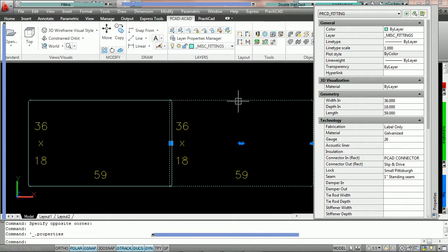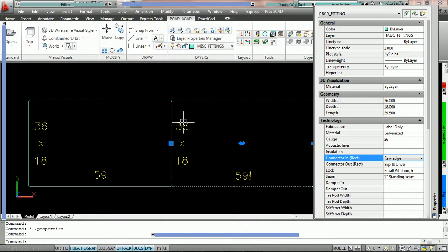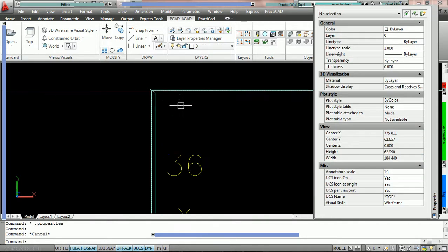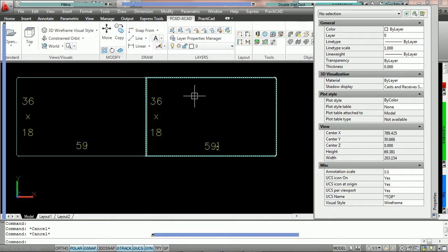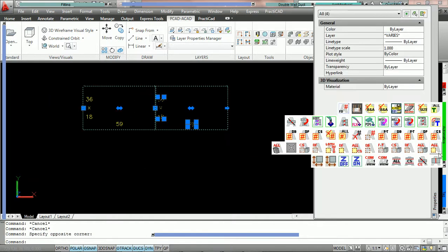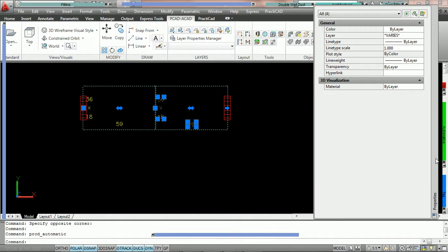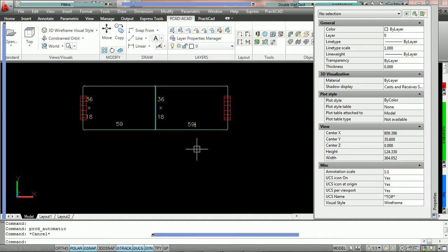Now, if we were to switch this connector in to raw edge, you'll notice that PractiCAD does not change the PCAD connector from this duct. And the reason why is, even though when you zoom in we have two different connectors, we've said that those connectors are compatible. And because of that, we can make an edit. We can even run a duct line check. And when we run the duct line check, you can see that it's only marking the ends of the fitting. There is no break. That is an acceptable connection to PractiCAD because they're compatible.